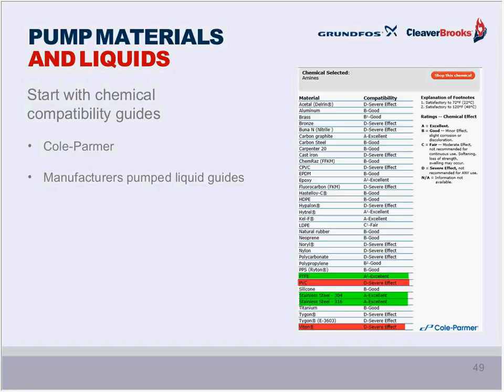These sources, whether printed or found online, are offered as guides, but the final decision on materials of construction must be based on discussions with the contractor and the chemical supplier, since the boiler manufacturer and pump manufacturer cannot be aware of all possible chemistries that exist out there today.